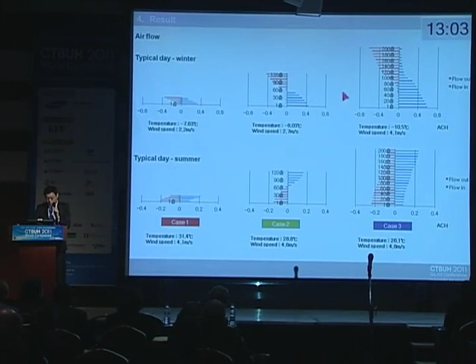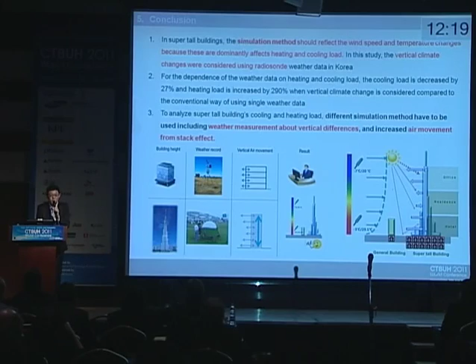So let me reach the conclusion. The first conclusion is that the simulation method should reflect, especially in tall buildings, the wind speed and temperature changes between the ground level and the higher level, because they are dominant effects on the heating and cooling load. In this study, the vertical climate change was considered using the radiosonde data. And the last thing about the calculation is the weather measurement about the vertical differences and air movement from the stack effect. Those both things are very important. So when simulating the building, these things have to be considered. Thank you for listening. This is the end of my presentation.